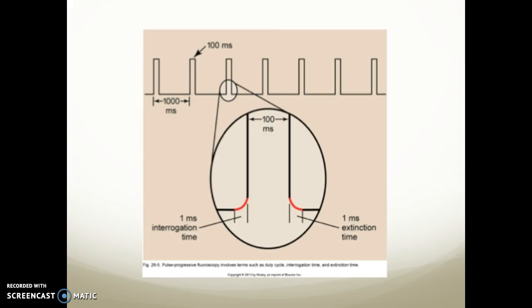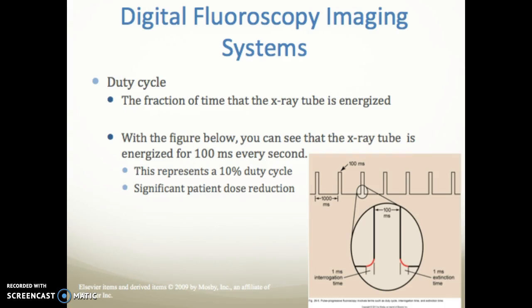This gives you an idea: the entire cycle is 100 milliseconds, with about one millisecond interrogation time and one millisecond extinction time. The duty cycle is the fraction of time the x-ray tube is energized. With the figure shown, the x-ray tube is energized for 100 milliseconds every second, representing a 10% duty cycle — really important for reducing patient dose.